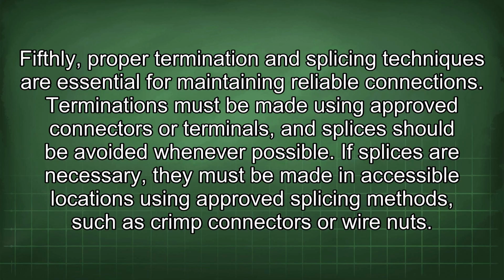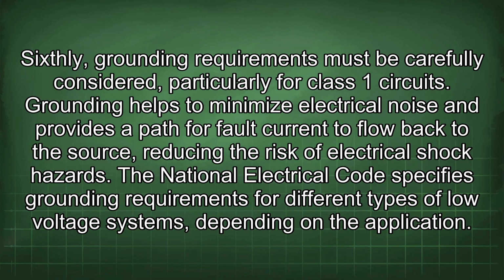Fifthly, proper termination and splicing techniques are essential for maintaining reliable connections. Terminations must be made using approved connectors or terminals, and splices should be avoided whenever possible. If splices are necessary, they must be made in accessible locations using approved splicing methods, such as crimp connectors or wire nuts. Sixthly, grounding requirements must be carefully considered, particularly for Class 1 circuits.